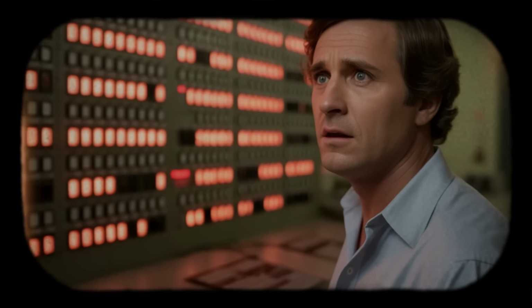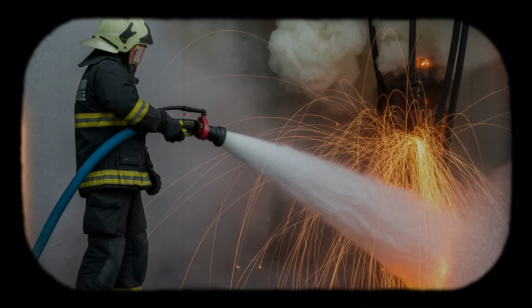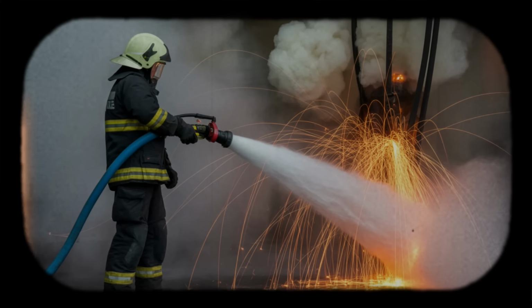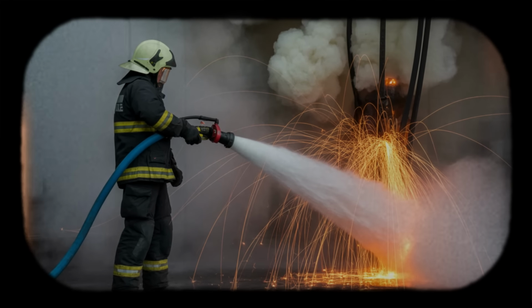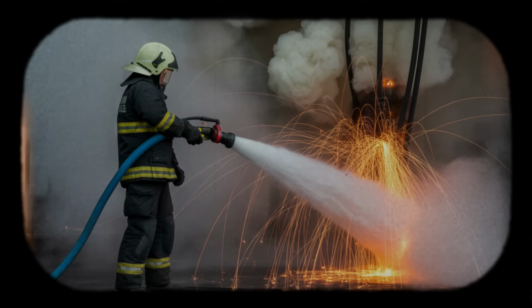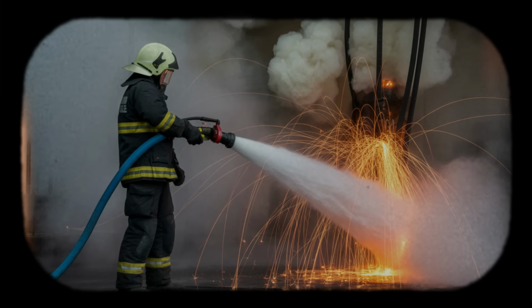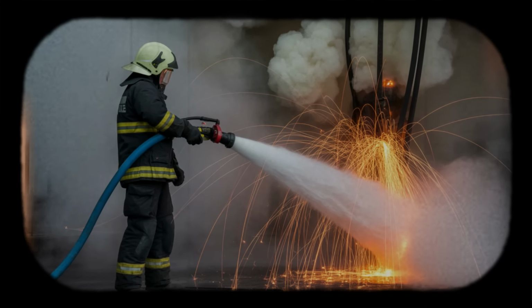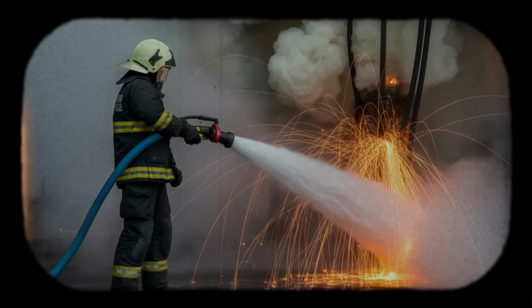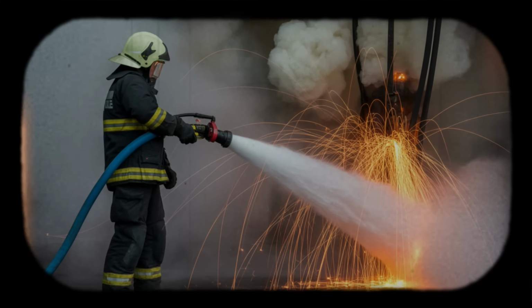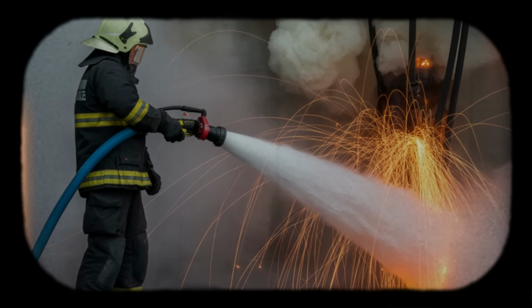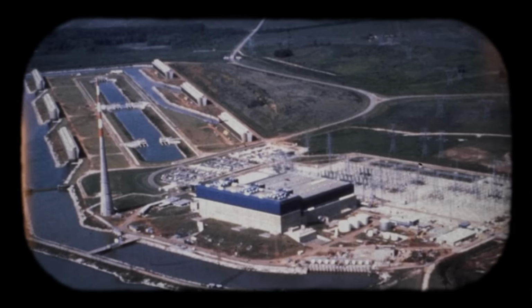1:26 to 1:40 in the afternoon. Throughout Browns Ferry, operators deploy personnel to physically inspect valves, pumps, and alignment markings. Manual verification is intended as a backup method, a fallback procedure used when instrumentation is suspect. It is not designed to be the primary mode of operation during an active emergency with fire-threatening safety systems.